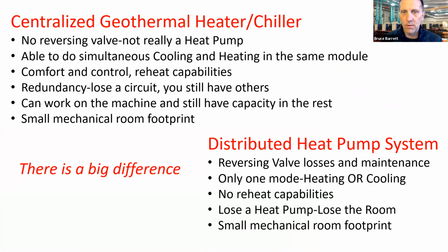Now, I mentioned centralized geothermal. Many of you are probably familiar with distributed heat pump systems, where each room or section of a building might have a heat pump up in the ceiling or in a wall casing. Each one of those distributed systems have reversing valves, so they're either cooling or heating. With a centralized system, we could have a reheat system with a cooling coil and a heating coil. We can leverage that simultaneous benefit, and we're also offering a lot of redundancy. If a distributed heat pump system goes down, you lose that section of the building. You're not able to do any reheat dedicated in that building. Centralized, you've got a mechanical room, you've got redundancy built in, and you can do reheat capabilities.